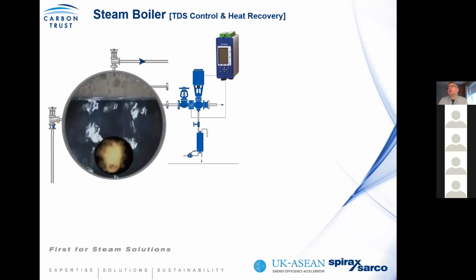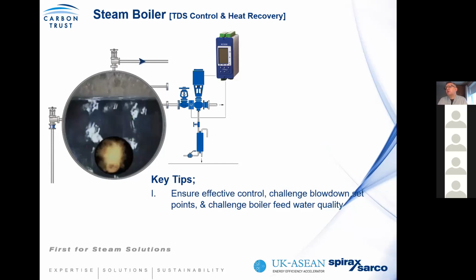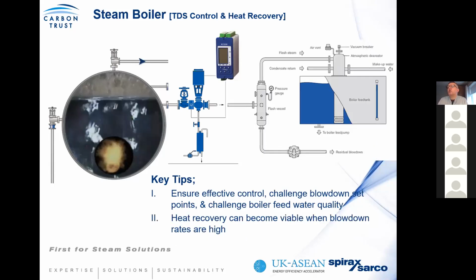However, if that is the case, what you should be doing is looking at the quality of water and seeing what can be done to improve it. And if, for example, where you have to control to silica or alkalinity, you have to increase the frequency or the amount of blowdown, then you should be looking at recovering this energy. Because what we have done for customers is take this high pressure condensate into the flash vessel, which we introduced in the fundamentals, where you would generate flash steam, and you would use the flash energy to offset the need for steam in your boiler feed water system, for example.